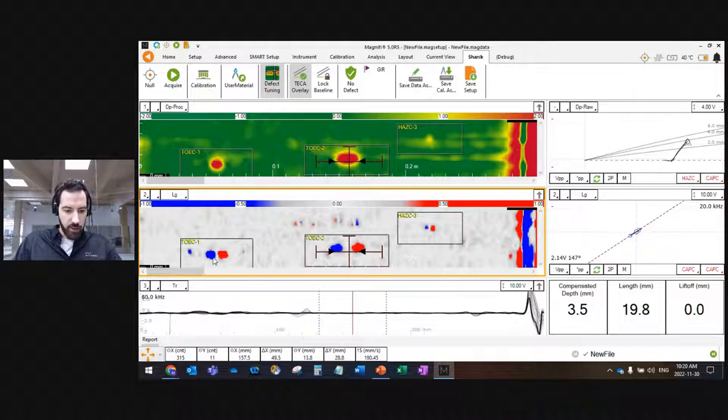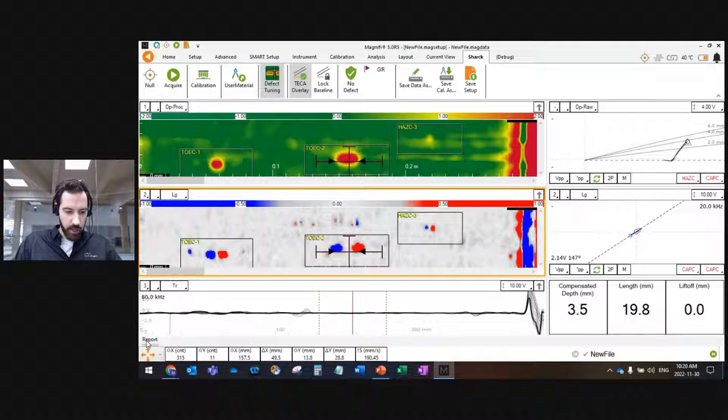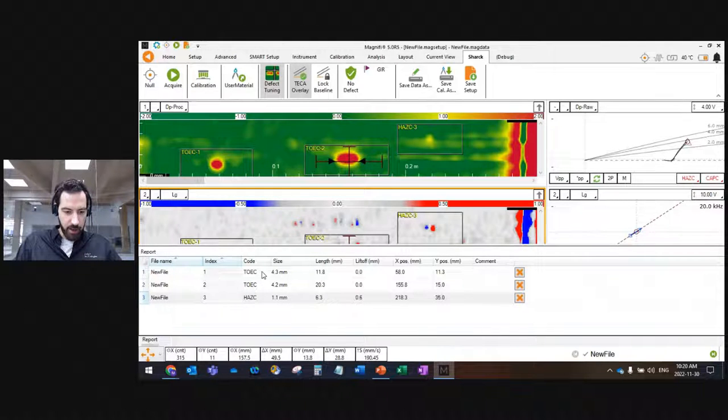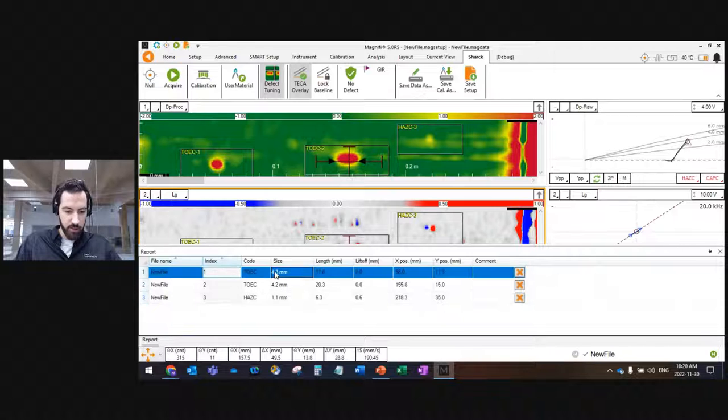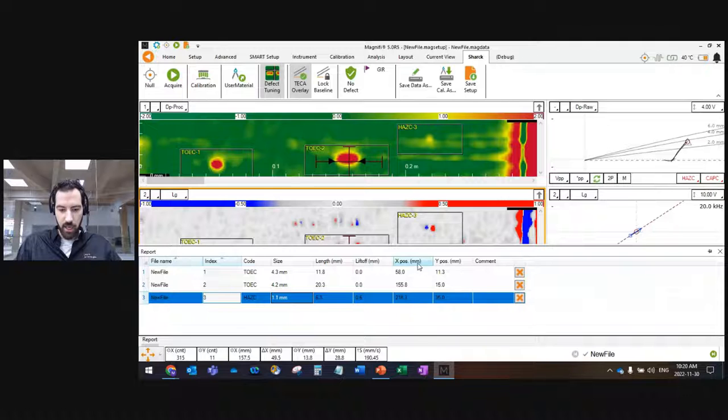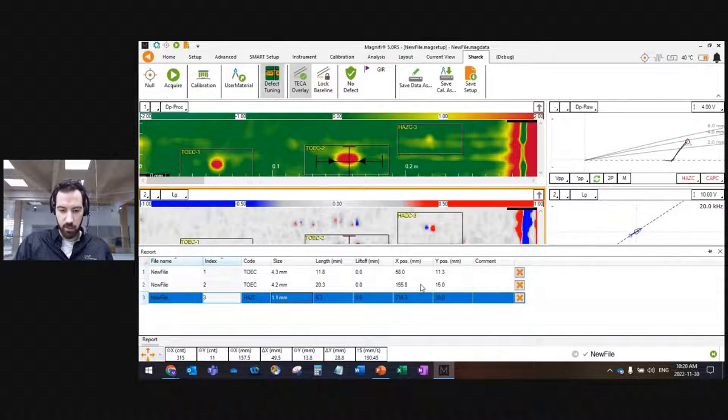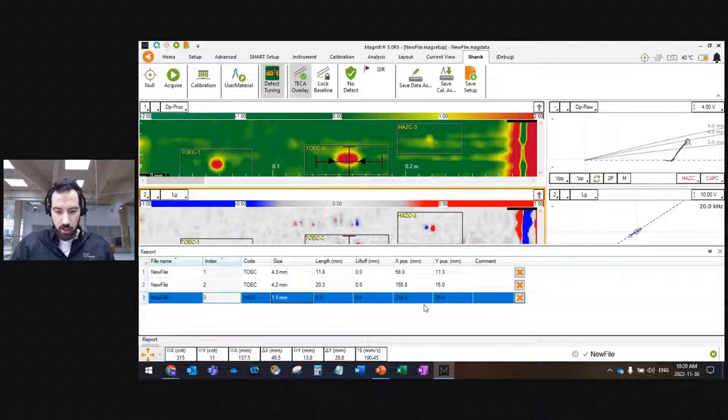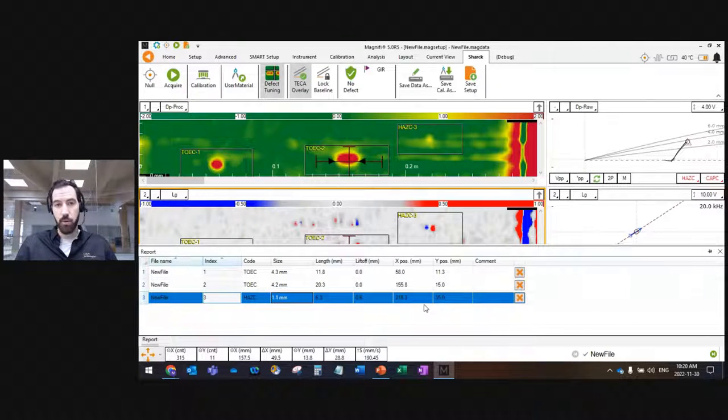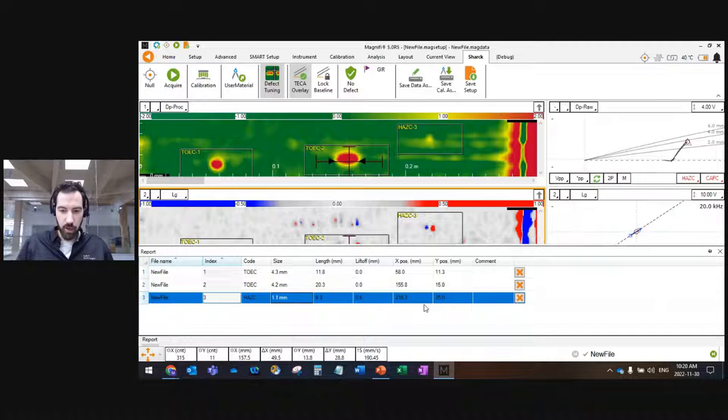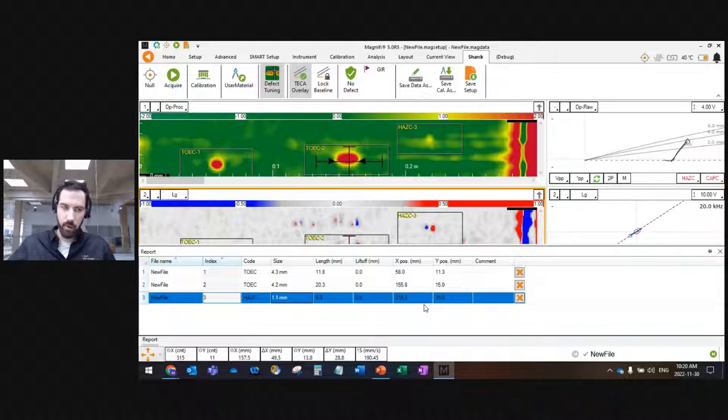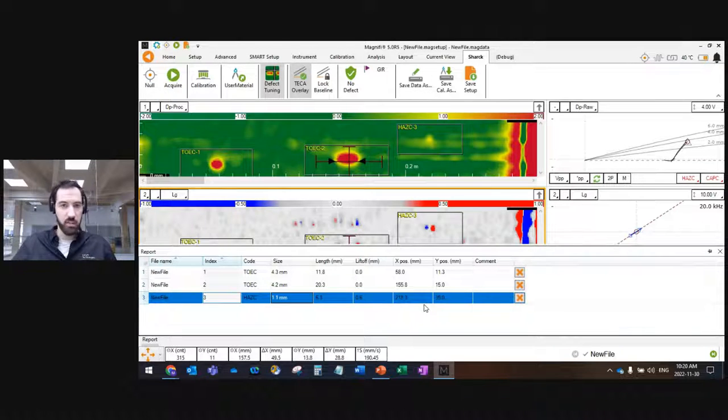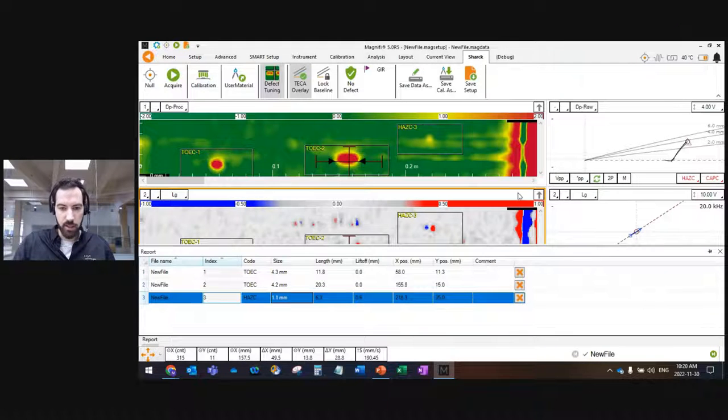At the end now, I've added my three indications. When I click on the report tab at the bottom, I have my three indications. They each have a size, 4.3, 4.2, 1.1, a length, a local liftoff, and a position. So if I scan a really long weld, I will have exactly the position. This report, you can export this as PDF right off the instrument. When you're in the field with your portable instrument, you can create a PDF, put it on a USB or transfer it via Wi-Fi, send it to your client, and be done with the inspection right there.